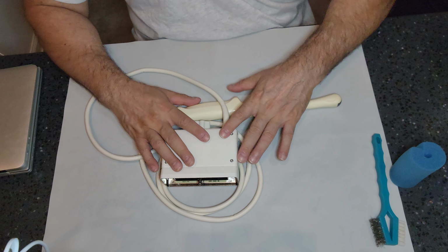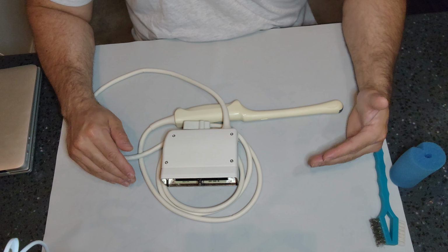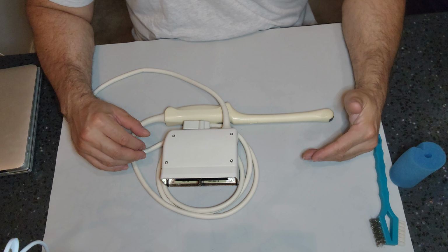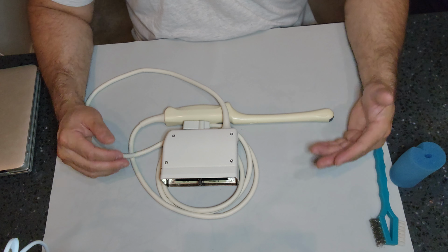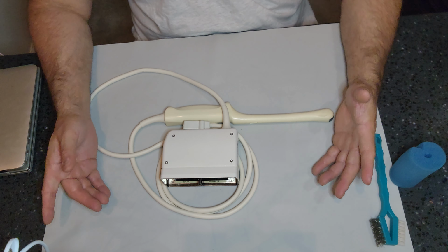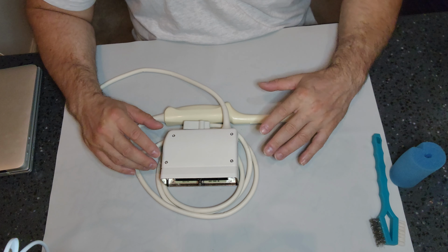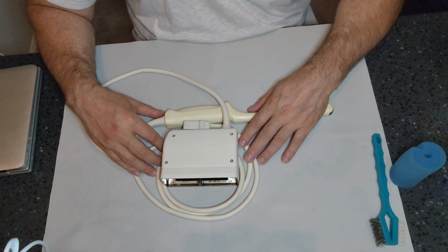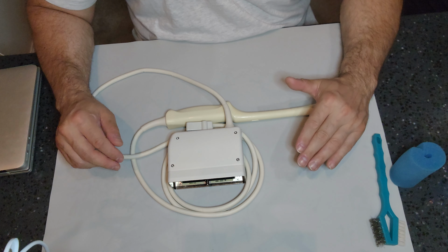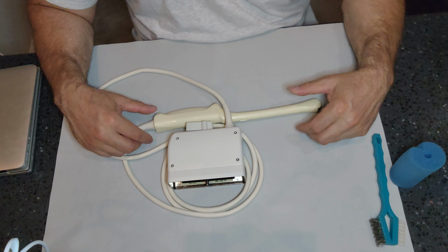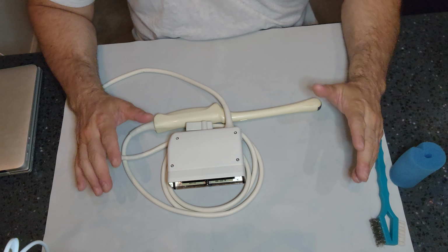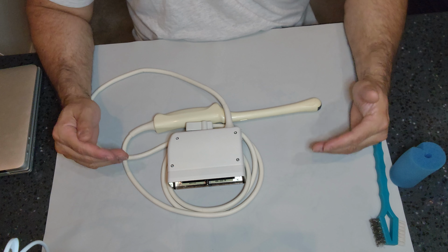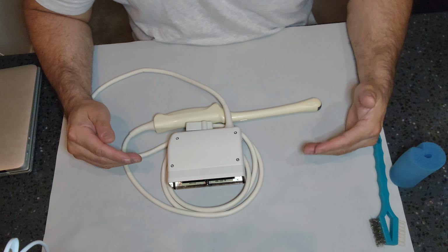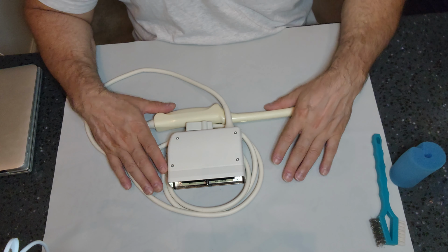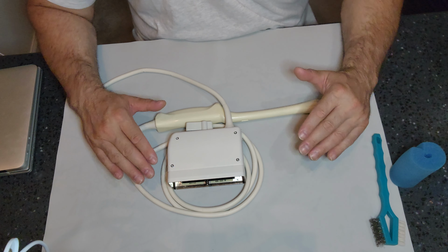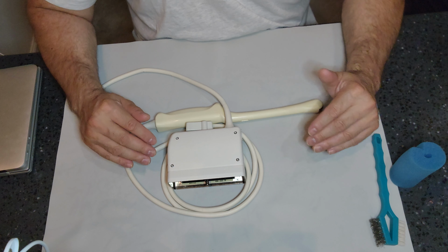But do we know what the probe is used for is first on the list. Why do I ask that? Well, because the Spaulding classification tells us how to further process these items. Now, I'm going to give my opinion. I believe probes or anything that touches the mucous membrane should be a critical item. No questions asked on that. The mucous membrane is considered a semi-critical item, and high-level disinfection is at best suggested. Sterilization, you can sterilize the item if the item can withstand sterilization, but at lowest disinfection, it's high-level disinfection.